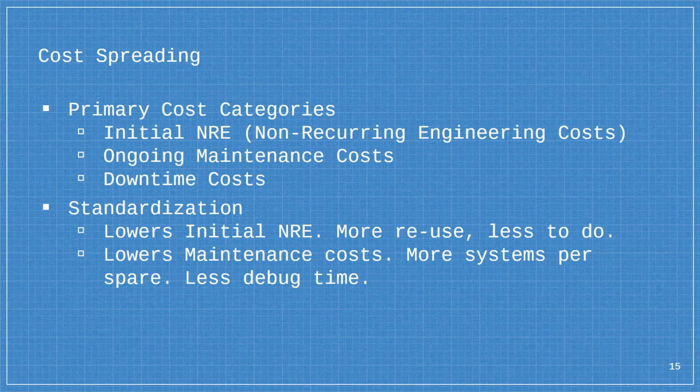If you've got 25 systems out there and they each got a $50,000 instrument in them, and then you've got one spare, then your spare cost per system is only $2,000. And in a lot of cases, you'll have enough excess capacity. You may not necessarily need a spare. You really should anyway, but you get the option that you can lower downtime by cannibalizing.